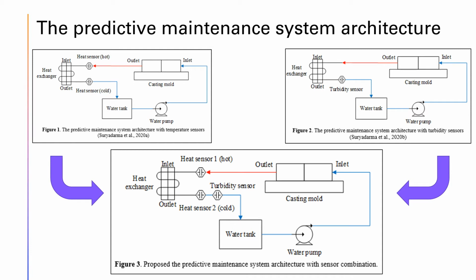And then this is figure 3, which combines the two predictive maintenance system architectures using a temperature sensor and a turbidity sensor. In the architecture with a combination of sensors, sensor 1, for hot sensing, is installed at the heat exchanger inlet, and sensor 2, for cold sensing, is installed at the heat exchanger outlet, and the turbidity sensor is installed at the heat exchanger outlet.